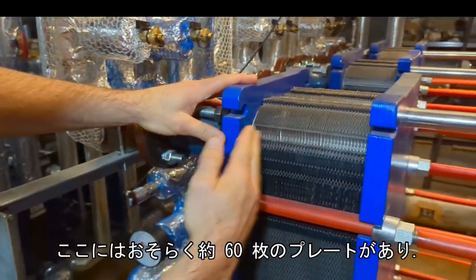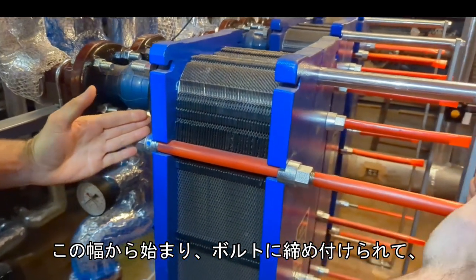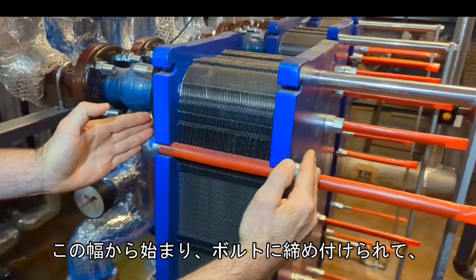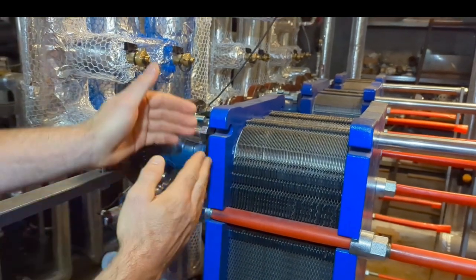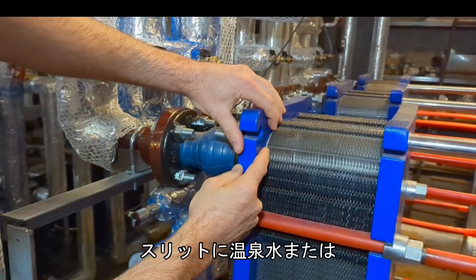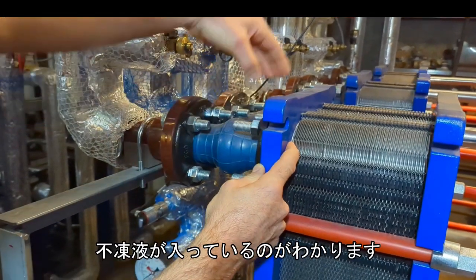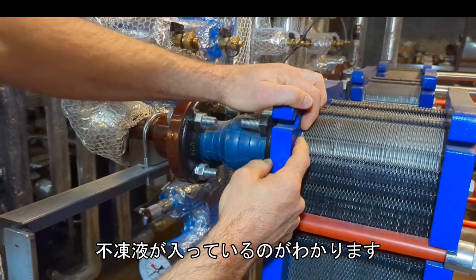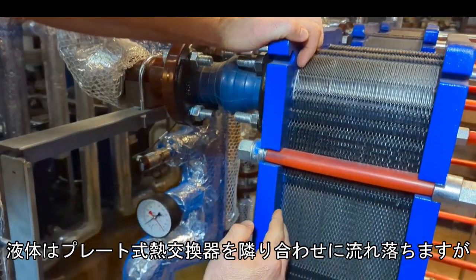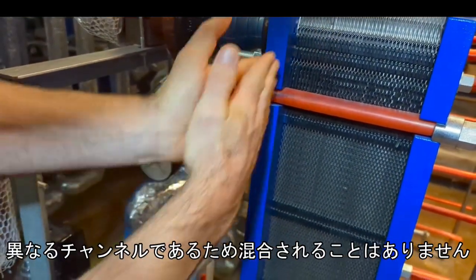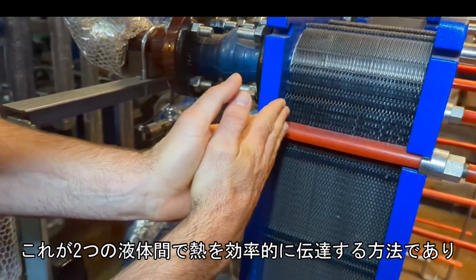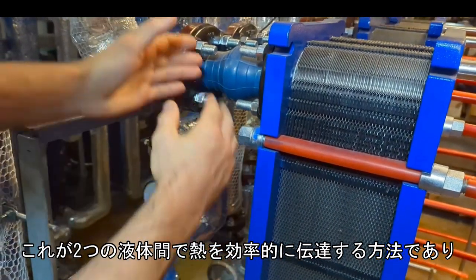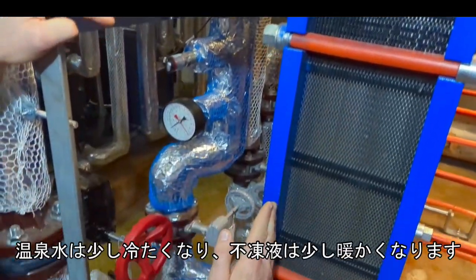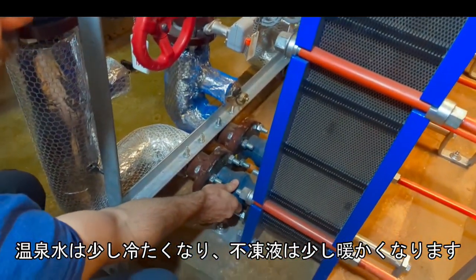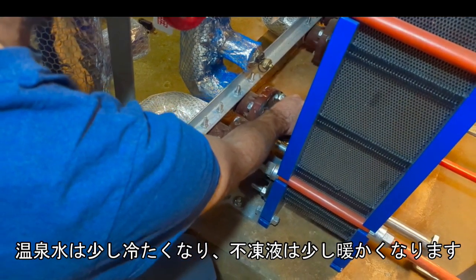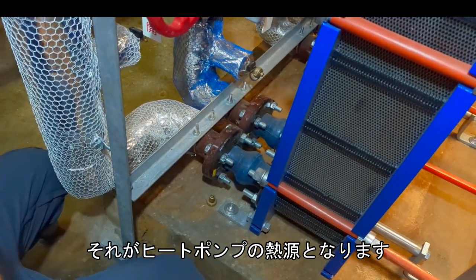We have probably around 60 plates here. They start out this wide and they get pushed together with these bolts and form very small compartments. Each compartment, you can see the slits, has either onsen water or antifreeze. They run down the plate heat exchanger next to each other, but they can't mix because they're in different galleries. This is a way of efficiently transferring heat between the two liquids. So they run down together, and the onsen water leaves a little bit colder and the antifreeze leaves a little bit warmer, and that's how we get energy across into the heat pump.